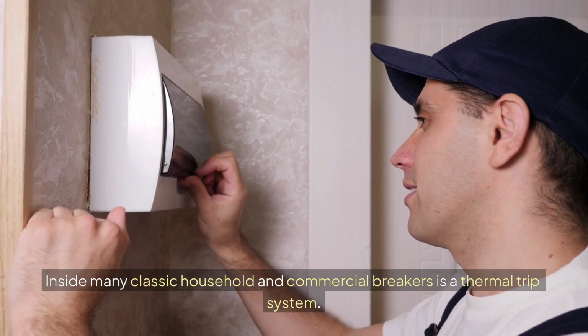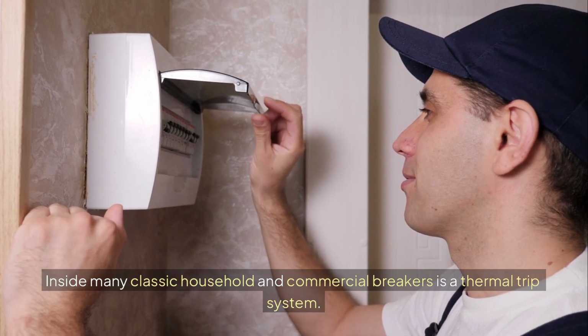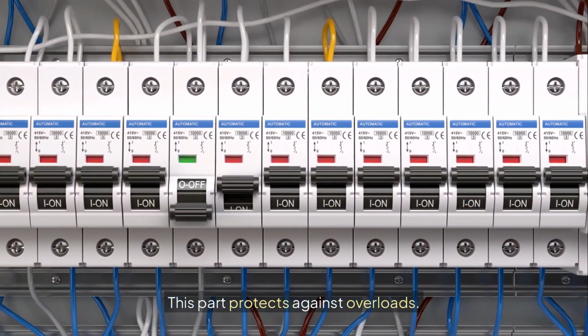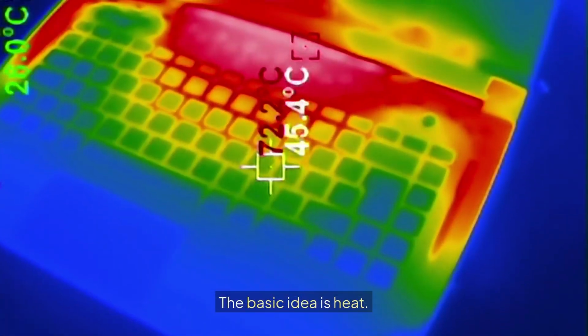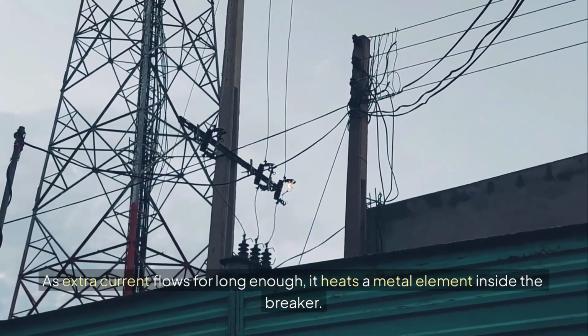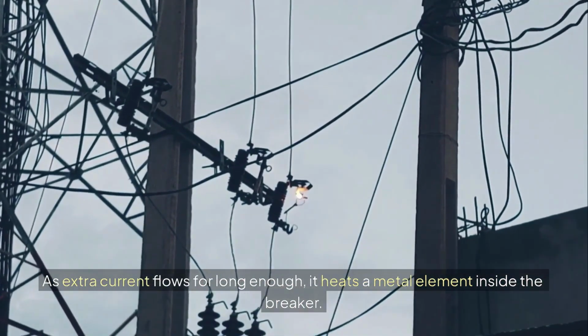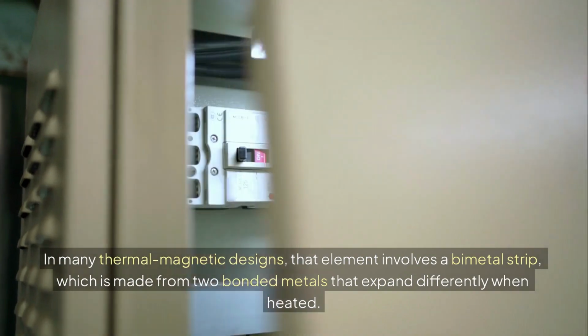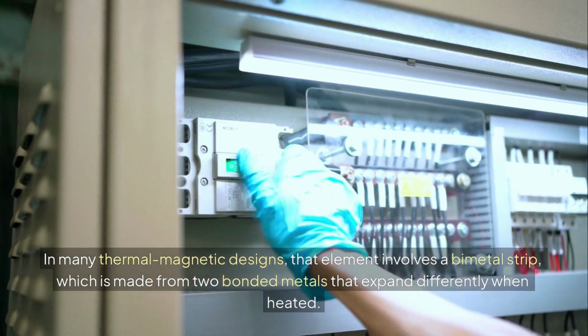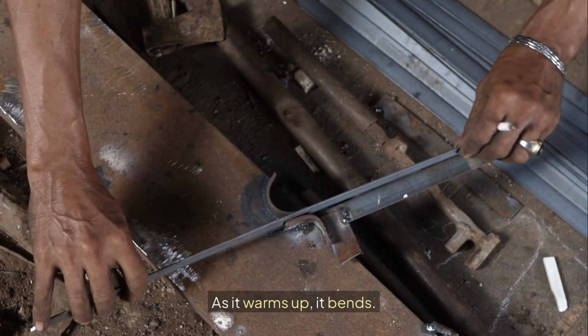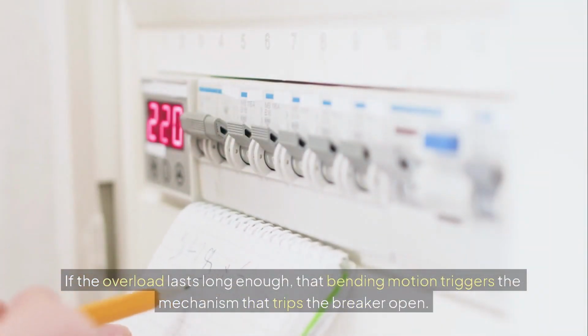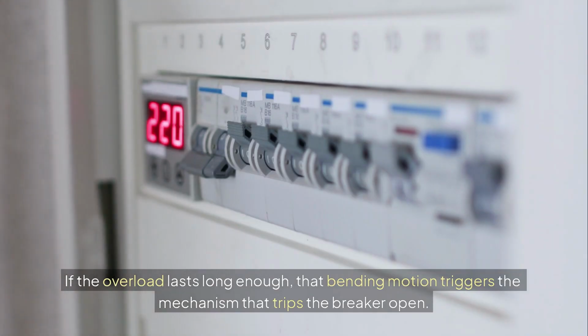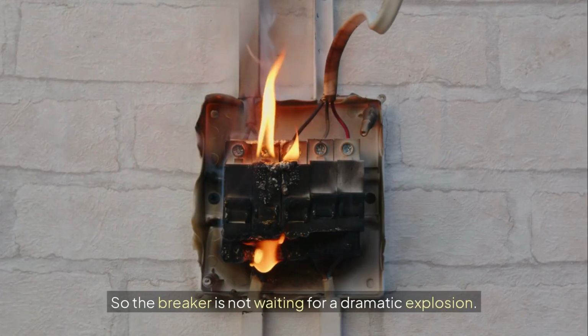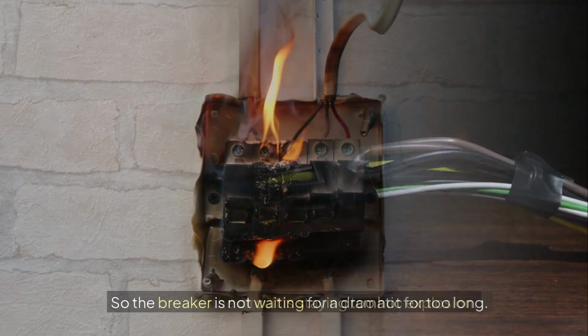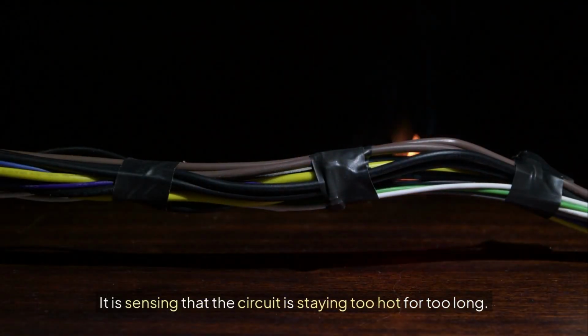The thermal trip: many classic household and commercial breakers use a thermal trip system. This part protects against overloads. The basic idea is heat. As extra current flows for long enough, it heats a metal element inside the breaker. In many thermal magnetic designs, that element involves a bimetal strip, which is made from two bonded metals that expand differently when heated. As it warms up, it bends. If the overload lasts long enough, that bending motion triggers the mechanism that trips the breaker open. So the breaker is not waiting for a dramatic explosion. It is sensing that the circuit is staying too hot for too long.